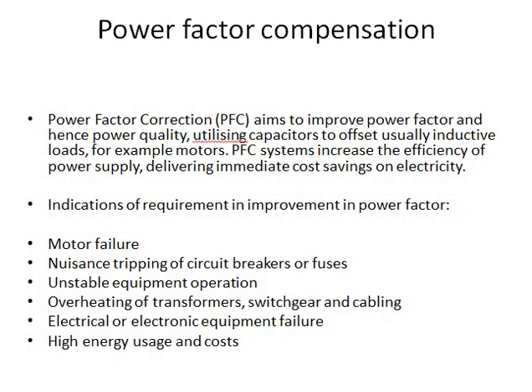What is power factor compensation? Power factor correction aims to improve the power factor and hence power quality, utilizing capacitors to offset usually inductive loads, for example motors. Power factor correction systems increase the efficiency of power supply, delivering immediate cost savings on electricity. Today, users as well as utilities, everyone is concerned about the present power factor. The objective is to improve the efficiency of the system, to reduce the heating losses, and to obtain optimum performance.